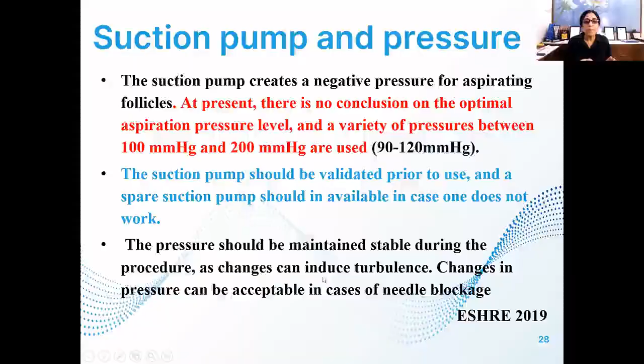Now, this is something which I also learned during the process when we started with these classes, going through the literature. This is something very interesting. When we talk of pressure, what is our target? Our target is to optimally aspirate an oocyte. Now, the aspiration setup might have an impact on the oocyte recovery rate. If the pressure is too low, maybe the M2 oocyte does not get dislodged from the cumulus. And if we use too much pressure, it could lead to damage. It has been seen that very high pressures can lead to breaking of the zona. So we need an optimum pressure, which would lead to aspiration of the oocytes with the least damage to the zona. So what is that?